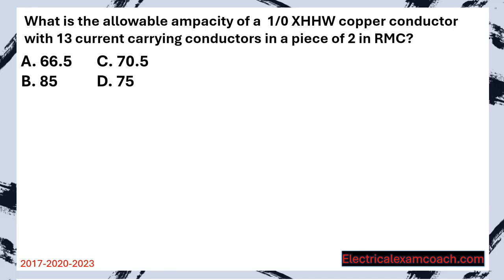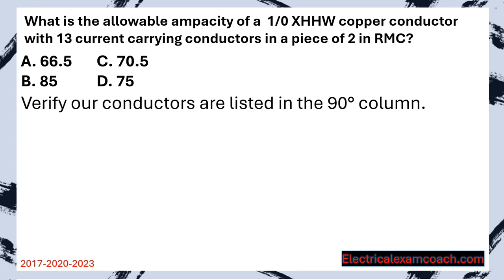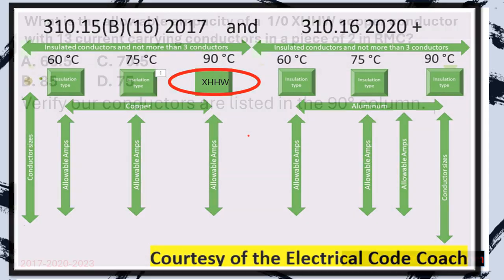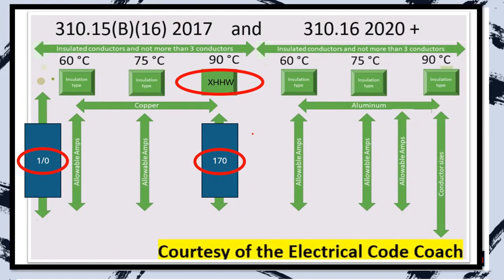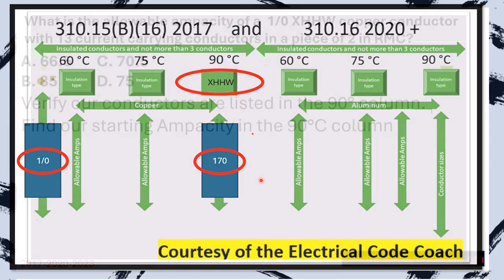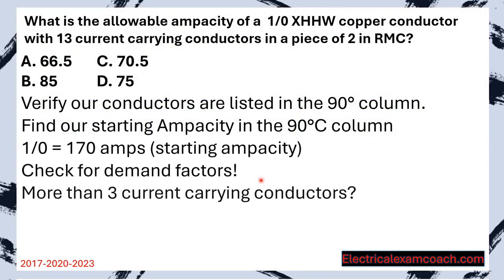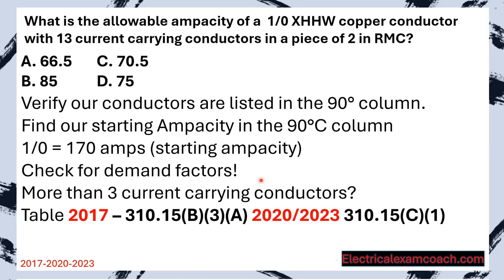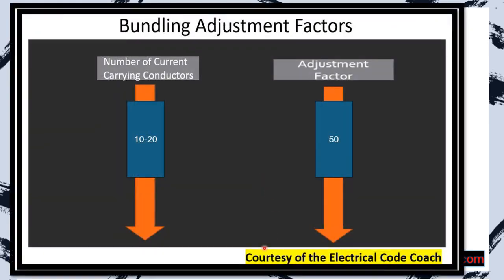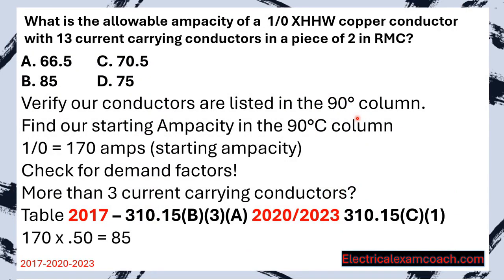Practice question: What is the allowable ampacity of a 1-0 XHHW copper conductor with 13 current carrying conductors in a piece of 2-inch RMC? Step one: verify XHHW is listed in the 90 degrees C column — it is. Step two: find the starting ampacity on the copper side of the primary ampacity table. Sliding down to 1-0 and crossing to the 90 degrees C column gives us 170 amps. Step three: there are more than three current carrying conductors, so we apply the adjustment factor. With 13 conductors we find the corresponding demand factor of 50%. 170 amps times 0.50 gives us a new reduced ampacity of 85 amps.